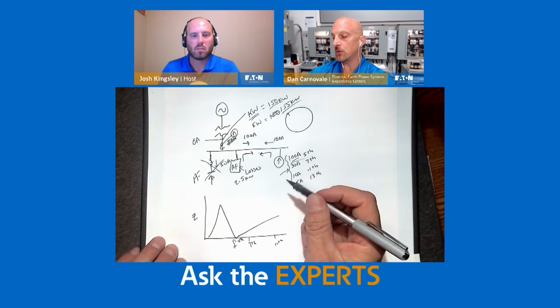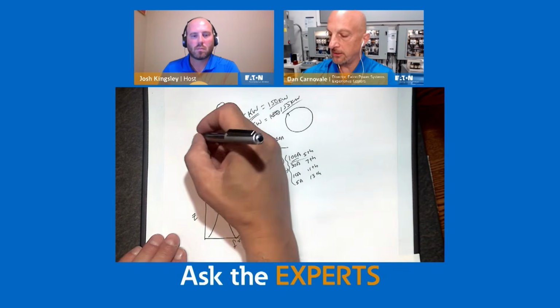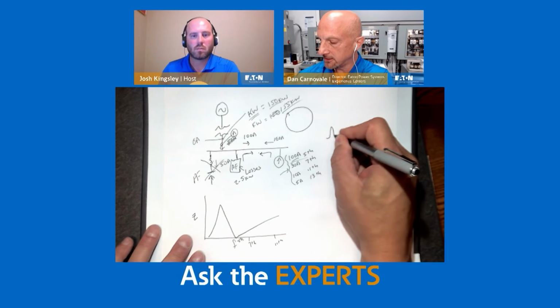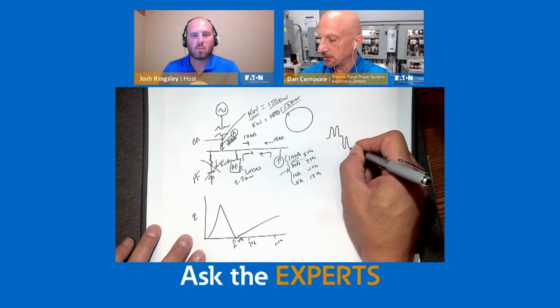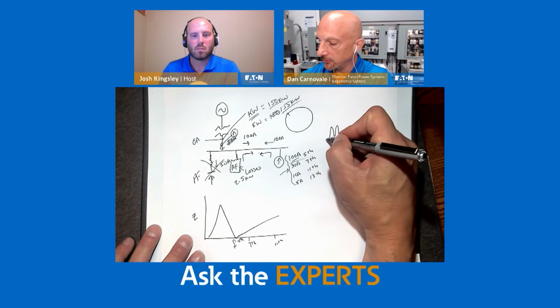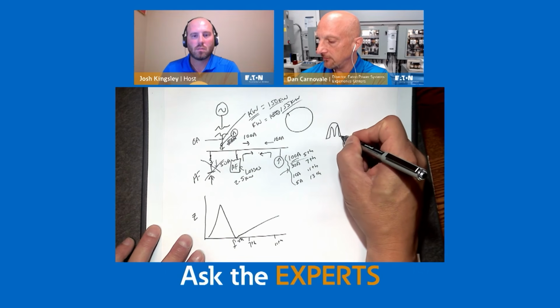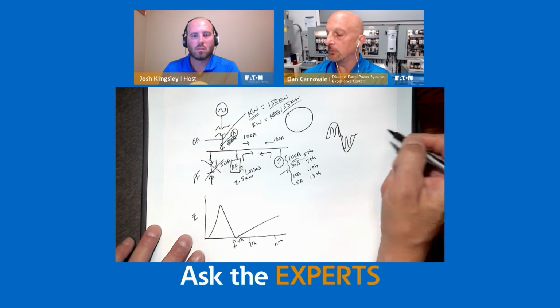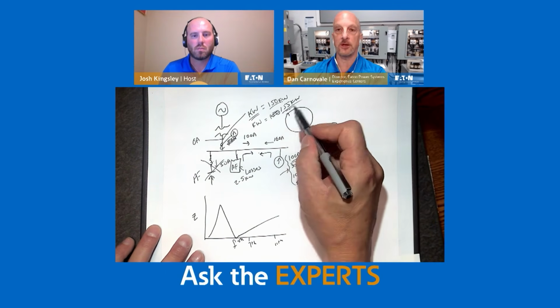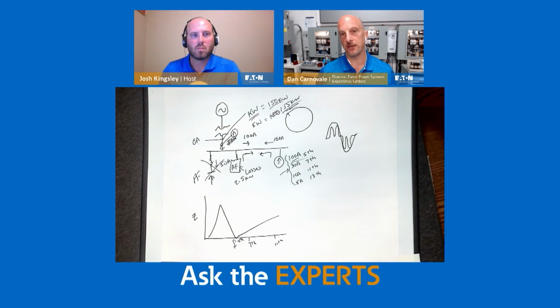So your current originally looked like this, very distorted. And what you're going to end up with is a really nice, clean sine wave, power factor corrected and everything. But you're going to pay for it with a little bit of losses. So get rid of harmonics, add a little bit of losses, but the benefit is there. And again, it's a system level thing, which is one of the things we address in the paper. Got it.